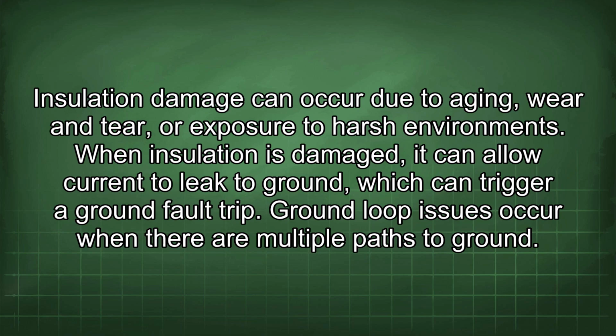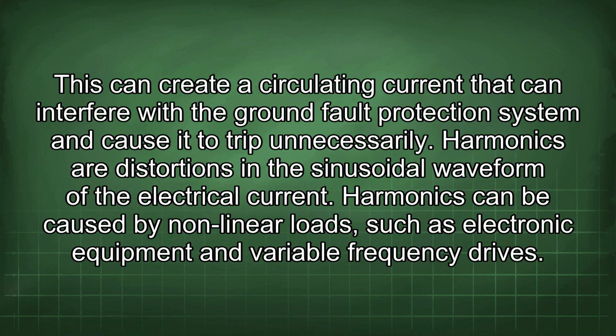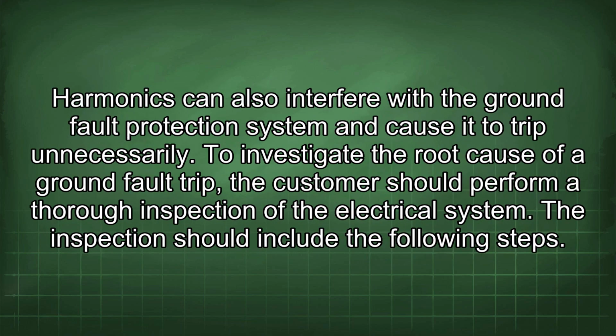Ground loop issues occur when there are multiple paths to ground. This can create a circulating current that can interfere with the ground fault protection system and cause it to trip unnecessarily. Harmonics are distortions in the sinusoidal waveform of the electrical current. Harmonics can be caused by nonlinear loads such as electronic equipment and variable frequency drives. Harmonics can also interfere with the ground fault protection system and cause it to trip unnecessarily.